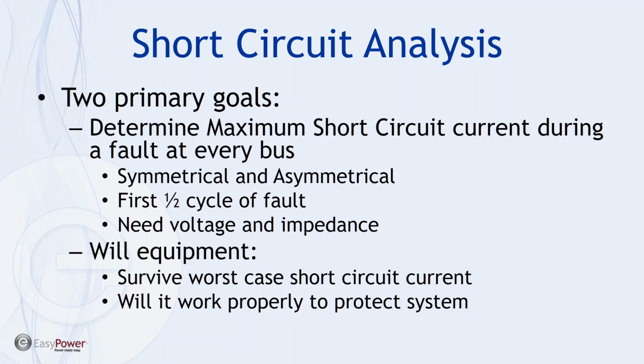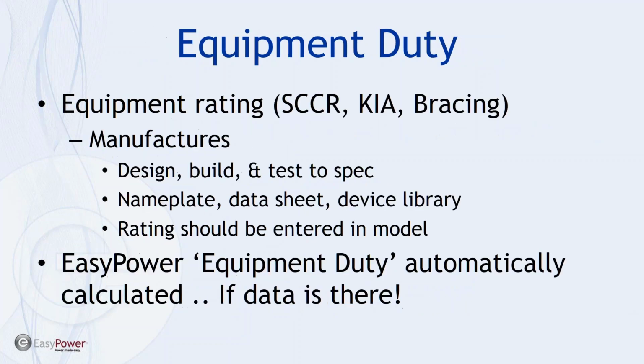Now, the second function of the short circuit analysis is, once we've determined what that worst case current is, and it will occur during the first half cycle of usually a bolted fault, the second question is, will our equipment survive and will it work properly in the system? And again, that particular feature or function is referred to as equipment duty.